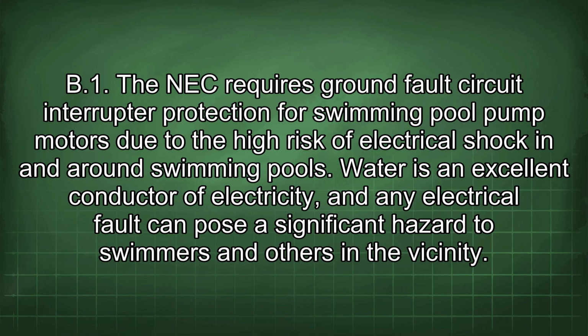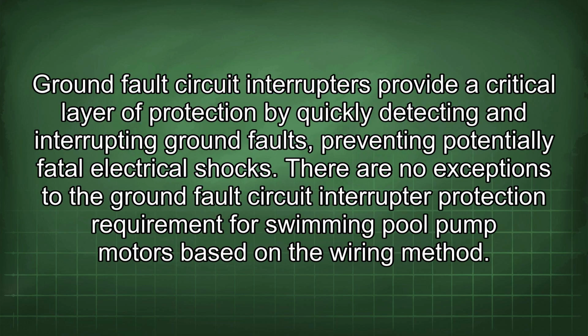Water is an excellent conductor of electricity, and any electrical fault can pose a significant hazard to swimmers and others in the vicinity. Ground fault circuit interrupters provide a critical layer of protection by quickly detecting and interrupting ground faults, preventing potentially fatal electrical shocks.